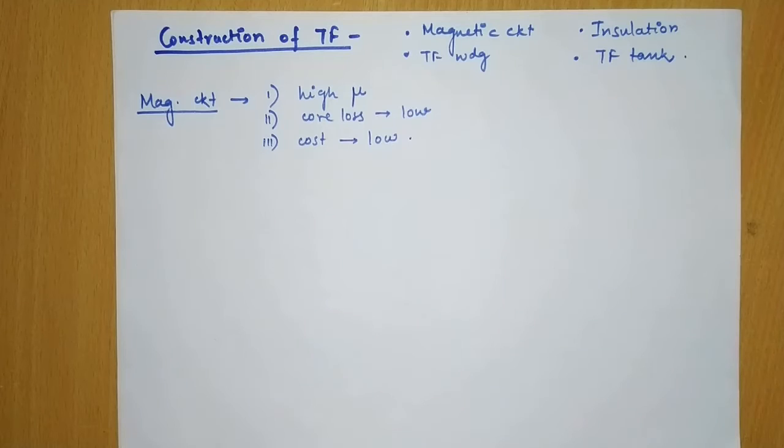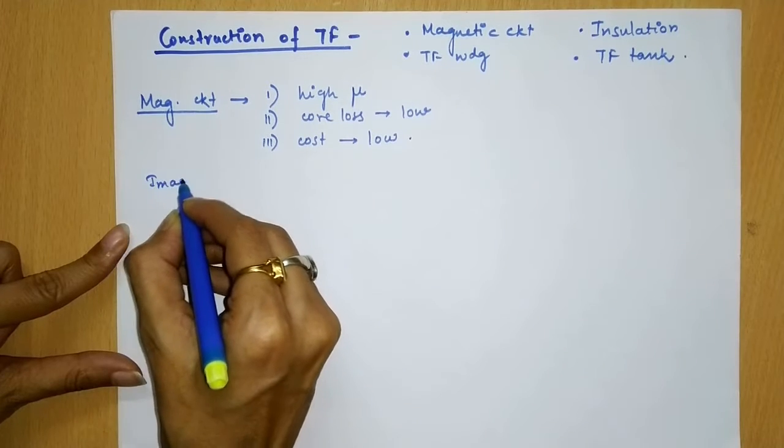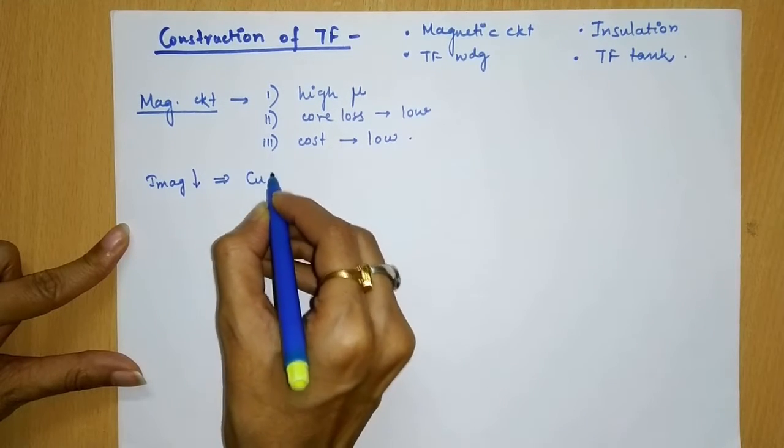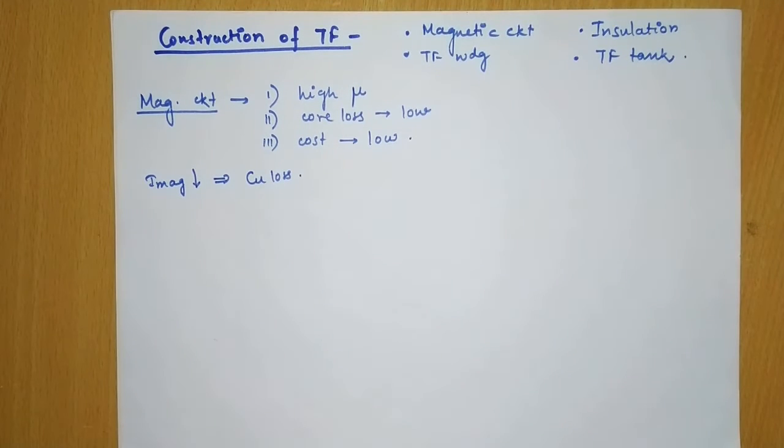What is magnetizing current? It is the component of the current drawn by the transformer winding in order to establish rated magnetic flux in the transformer core. Designing transformer with high permeability core medium can minimize the magnetizing current to a very low value. The advantages of less magnetization current demand are: if magnetization current reduces, then the copper loss can be reduced. Next, the operating power factor can be improved as the magnetizing current is a reactive component.